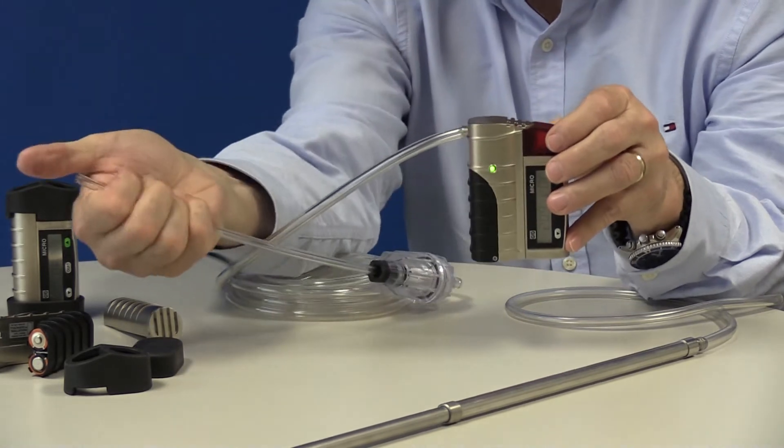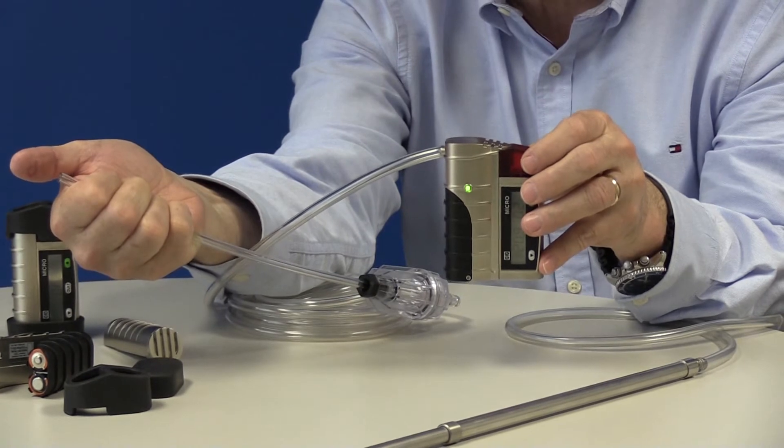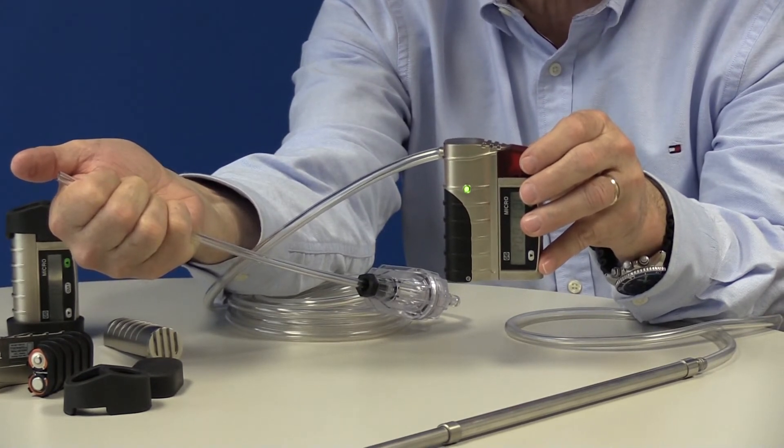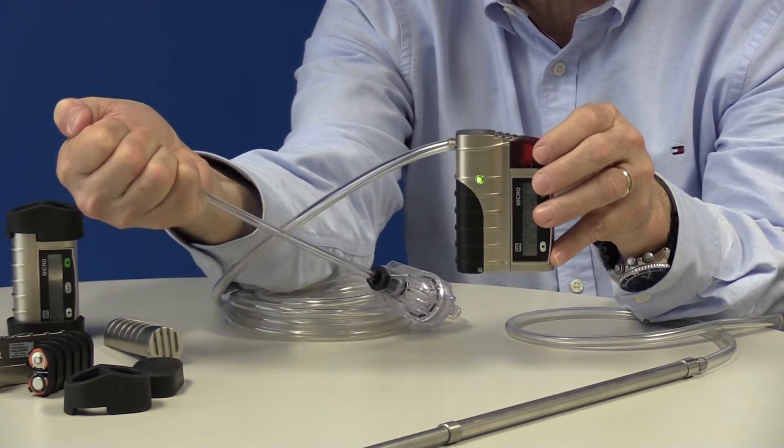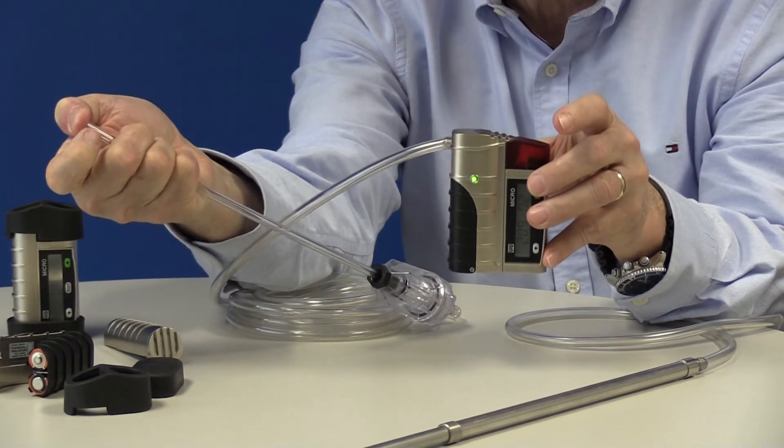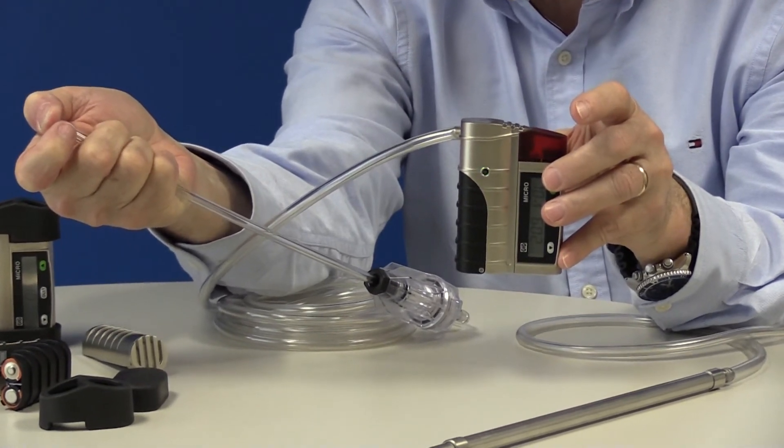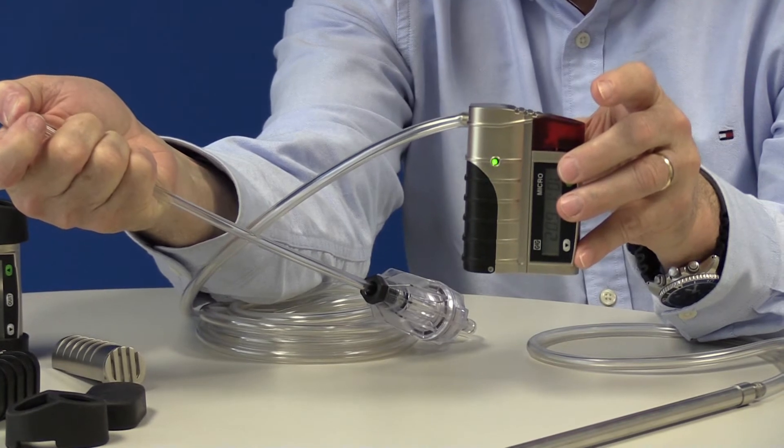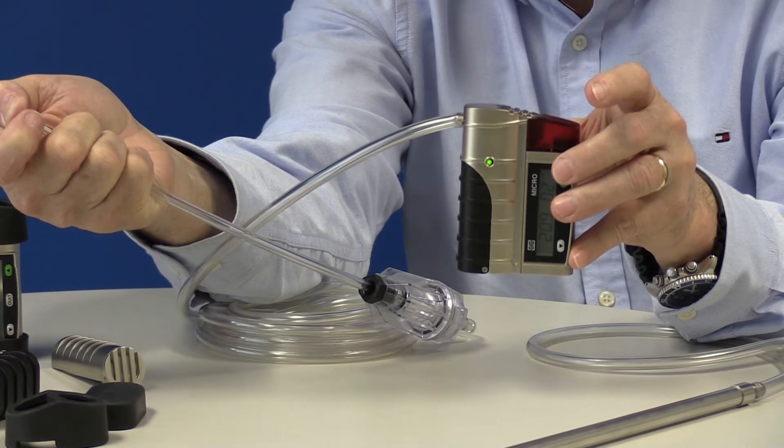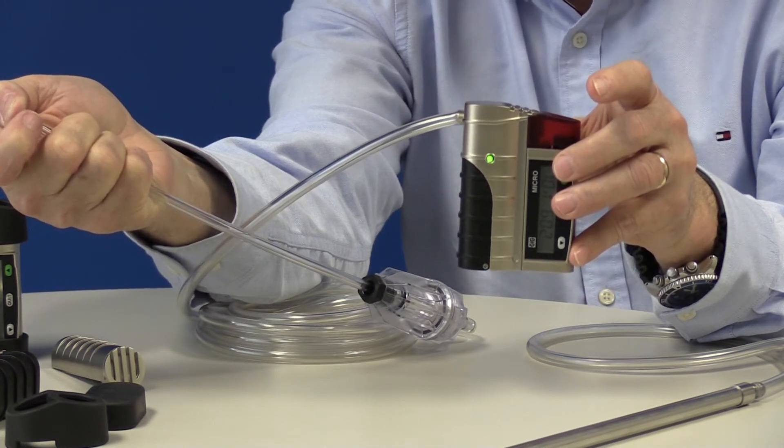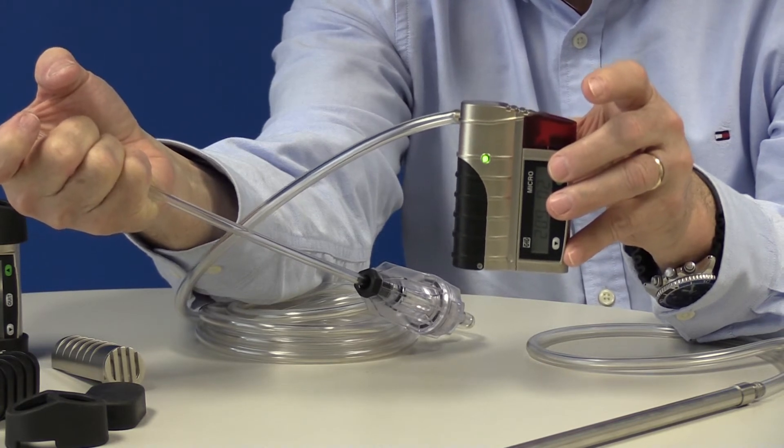The final step is to make sure that you don't have any blockages or leaks in the sample drawing system. And the way that we're going to do that is to cause a blockage by blocking the end of the probe. So you'll hear the pump struggle and eventually it will either shut down completely or labor and barely be running. And the green light will begin to flash to alert you to the fact that there is a blockage in the line.